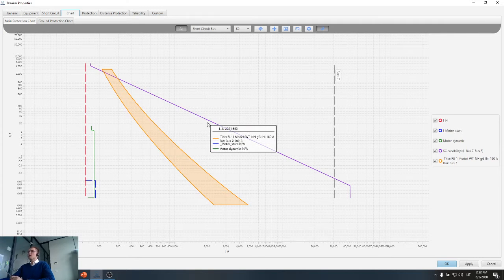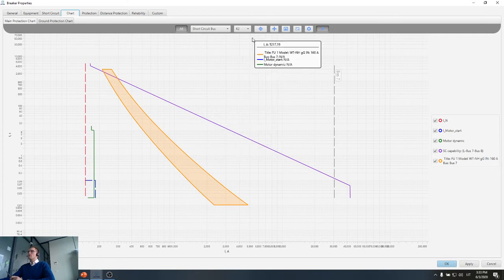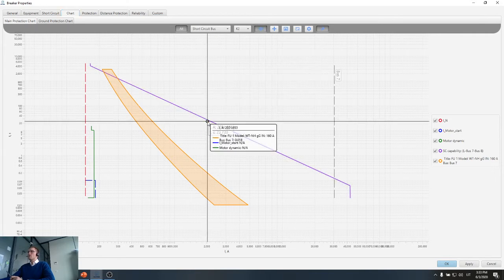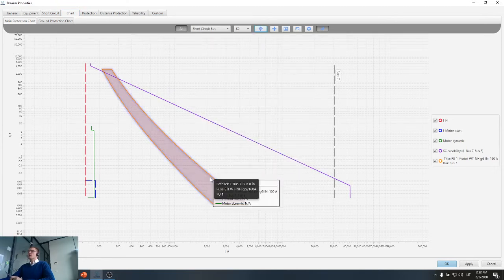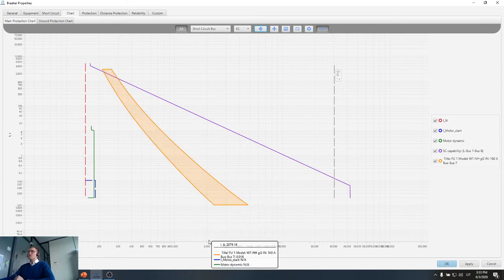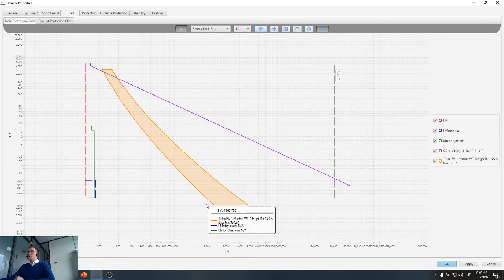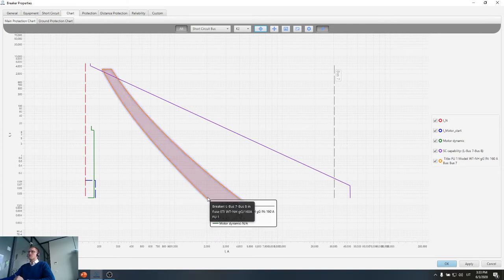We can see basically on the bar here. Let's turn it on. It's around 25 seconds. Yeah. So our protection device, in this case the fuse, should be capable to trip faster, and we can clearly see that in case of 2000 amps, our protection device fuse will trip in around 180 milliseconds, which is good. It means that it trips faster and protects our cable. So this is the idea regarding the protection selectivity chart.